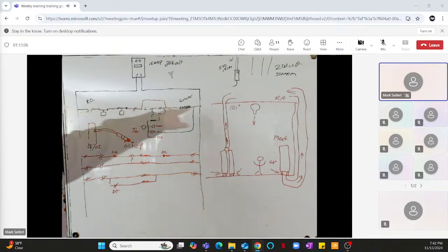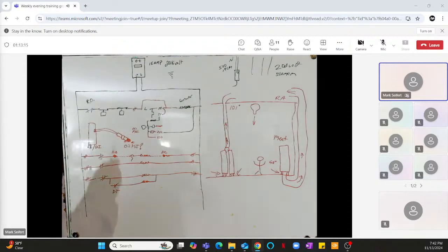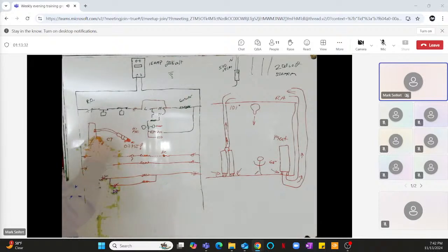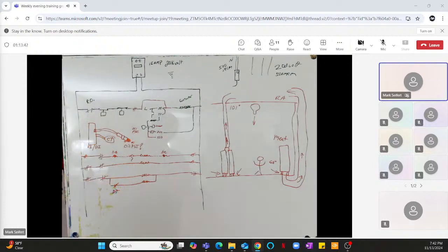It closes, tells the compressor to run. If the compressor is not running, or if it's running and there's no oil pressure, it's going to trip. So it's going to trip regardless. If the low pressure opens up, it's going to trip unless there's a CT built in. Now, mind you, on the E2s, and I don't know about the Danfoss, if it's got a CT built in, and that's another input, if the CT doesn't say the compressor is running, let's just say it calls for it to run, the CT says the compressor is not running and there's no oil pressure, it's not going to trip. So this is more software. This is just written in the program.